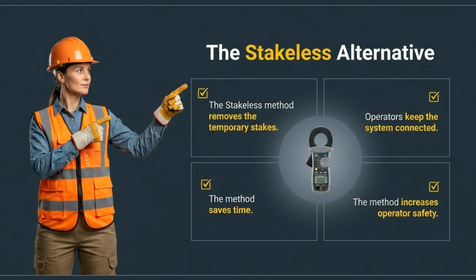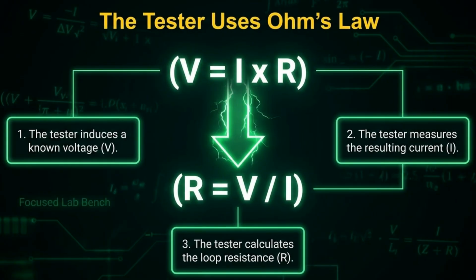The stakeless alternative offers a more efficient approach. It eliminates temporary stakes, keeps the system connected, saves time, and enhances operator safety. Stakeless testers utilize Ohm's law. The device induces a known voltage, measures the resulting current, and then calculates the loop resistance.